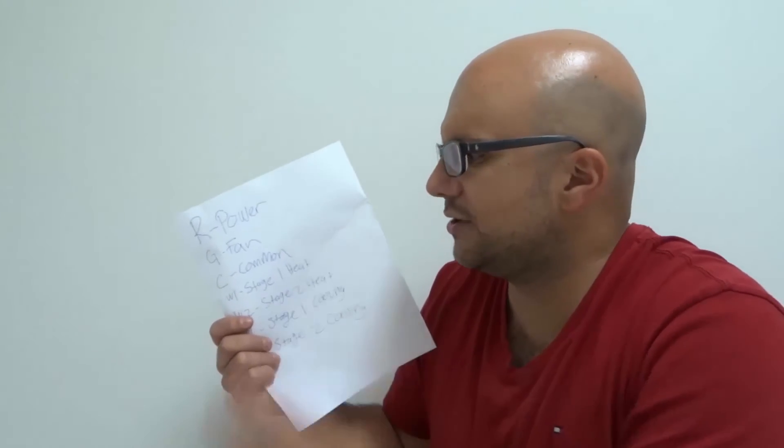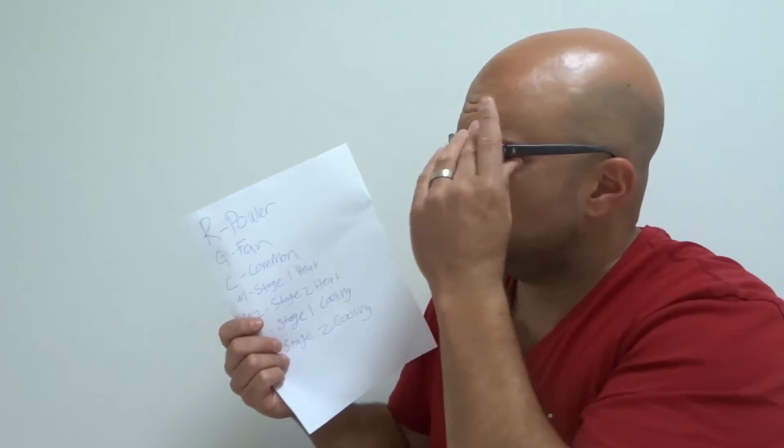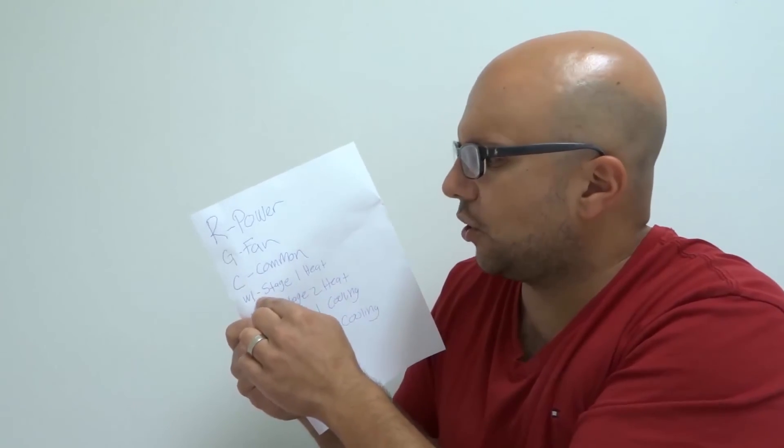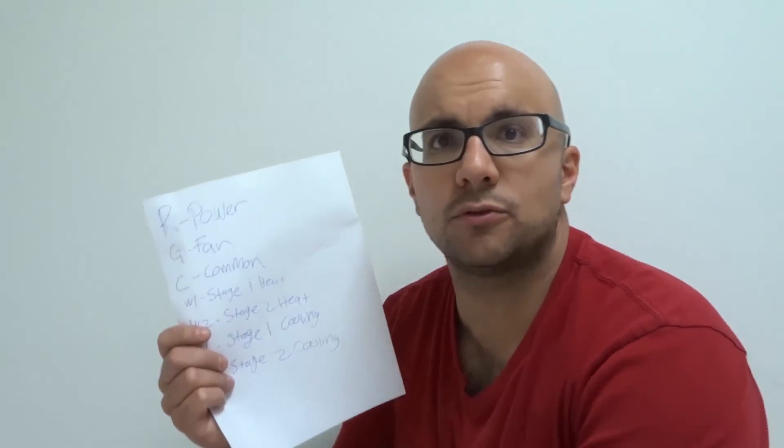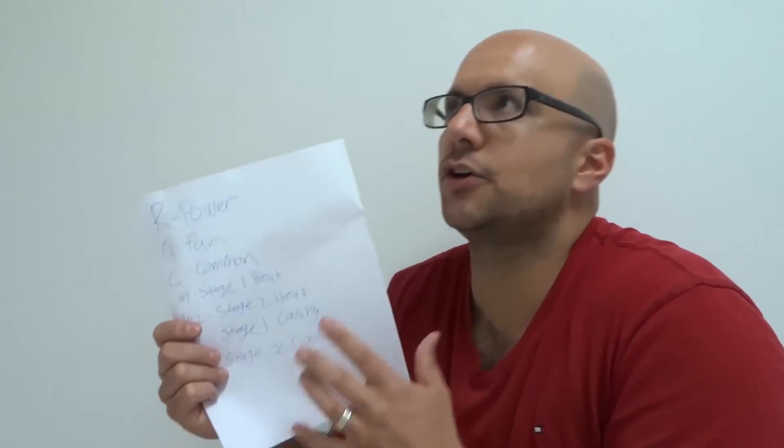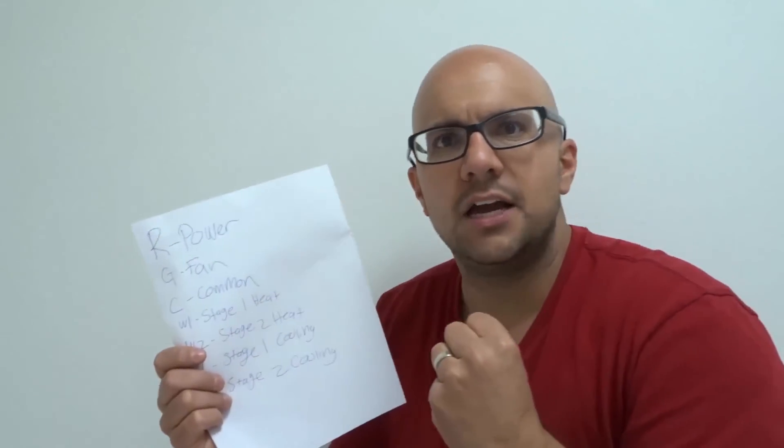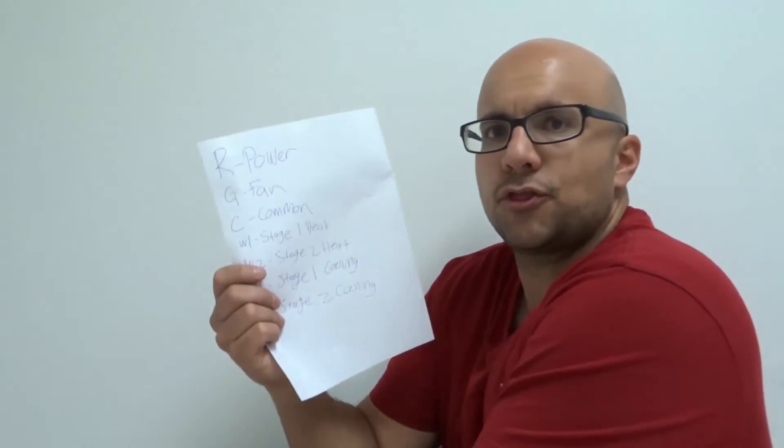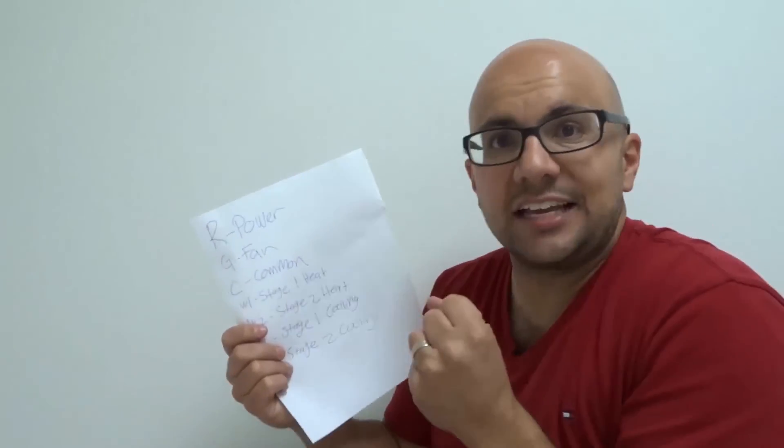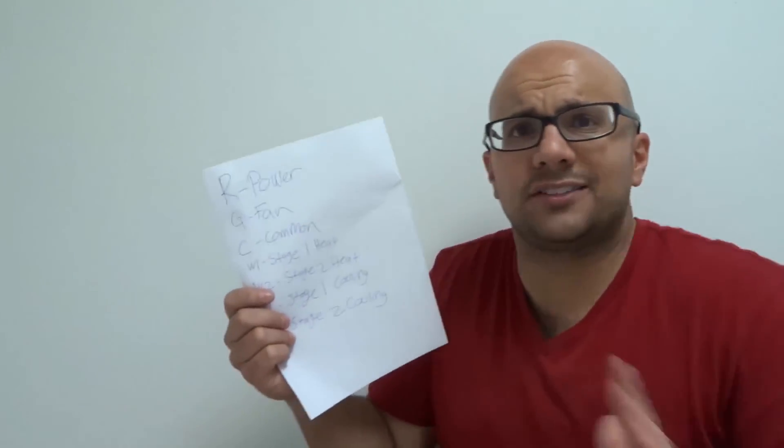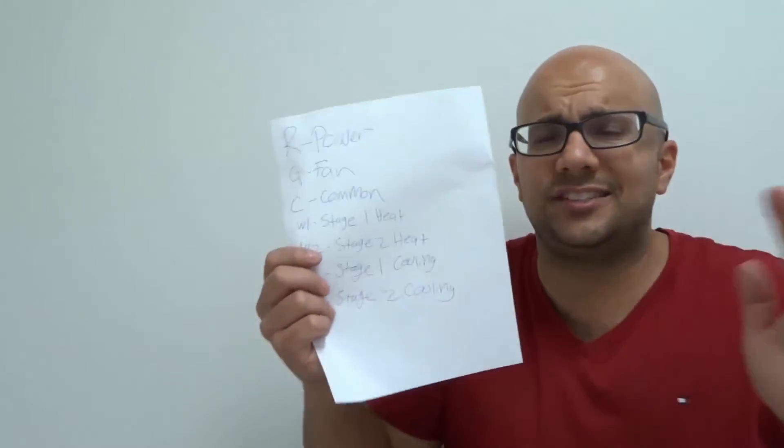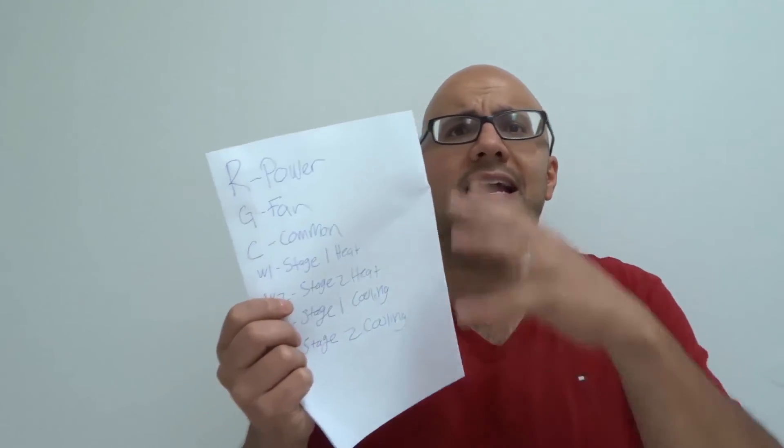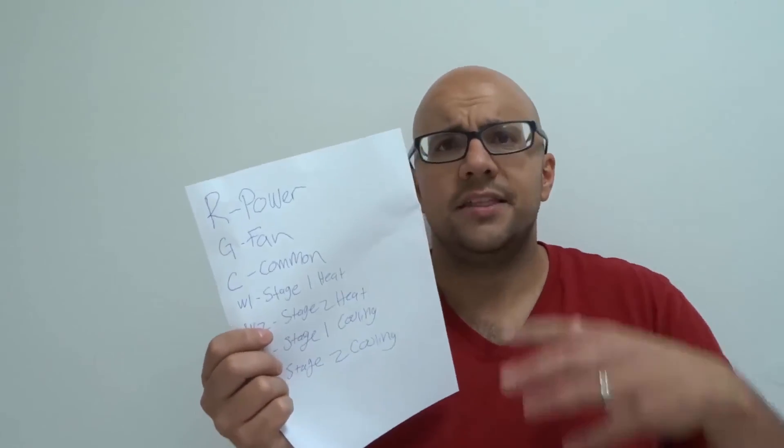Let's say you need your heat. So, your power is going to come up through your R wire, and then it's going to go down through your W1, which will turn on your Stage 1 heat. That's how your furnace, your thermostat will call for heat. We call it calling for heat because the power is coming up to the thermostat, and then it's asking. It's calling for Stage 1 heat through the W1 wire. That's how it works. It's literally that simple.